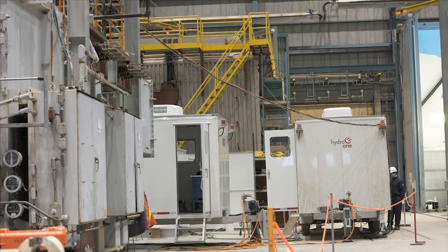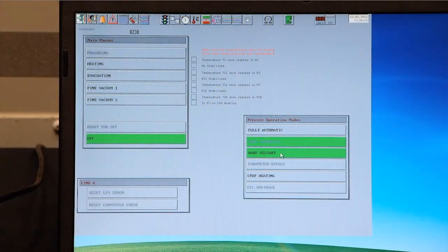This measuring phase should never be started after heating up the transformer. If this is done, then the temperature will not be correct and the transformer will be overheated, which may destroy the transformer. After switching off the process, it always needs to be restarted with the warm restart function, which keeps the initial resistance values and just remeasures the temperature of the transformer. It is extremely important that the warm restart is made, and not a new measurement.